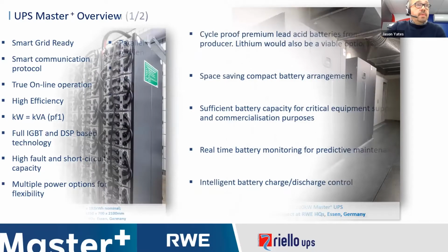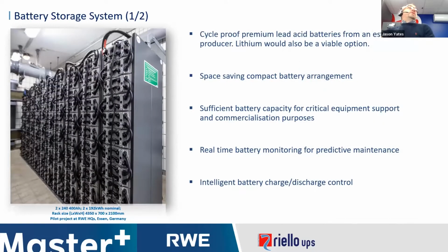Now, obviously, a UPS system is nothing without its battery system. The particular battery system that we used for this project was a cycle-proof premium lead-acid battery from a well-established producer. Obviously, for this kind of application, we could also use lithium, as this would also be a viable option. The main benefits of this system were that it offered significant space saving because it was a very compact battery arrangement. There was sufficient battery capacity for the critical equipment support and also for the commercialization purposes. The system had real-time battery monitoring for predictive maintenance and also intelligent battery charge and discharge control.